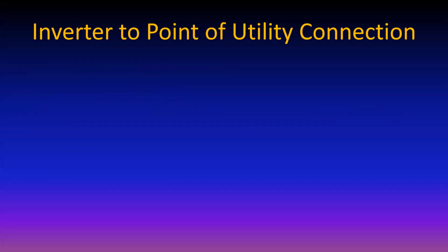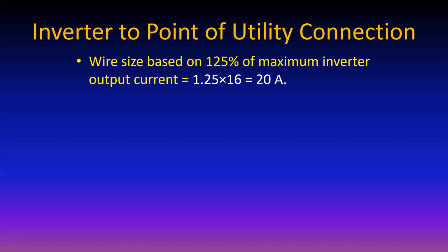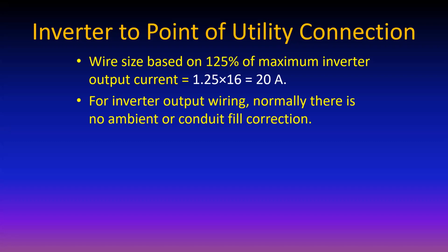Then wiring between the inverter and the point of utility connection. Again, 125% of the maximum inverter output current. So here we've got 16 amps out, 125% of that is 20 amps, so that means that you can backfeed a 2-pole 20 amp breaker. And that 2-pole 20 amp breaker will normally be located on the opposite end of the bus bar as the utility feed. And we'll draw a picture of that in a minute and show the reason.